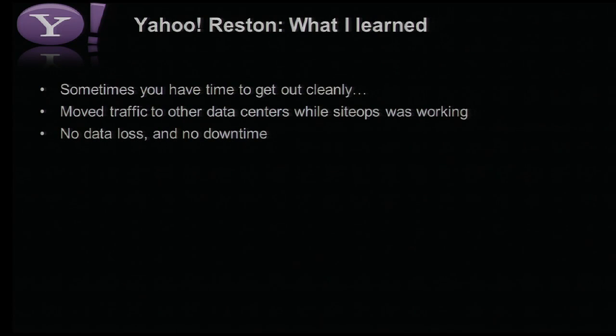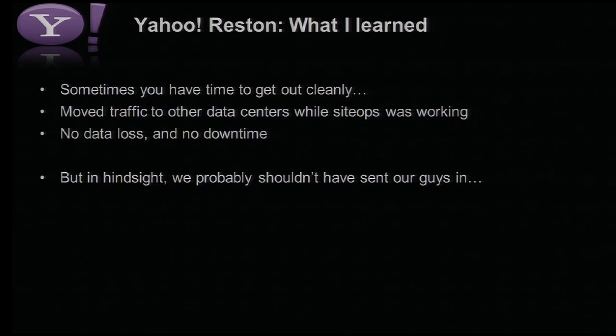Data center went up to 130 degrees within minutes. We were sending our site ops in 5-minute shifts to cleanly shut stuff down. Now, in that case, what I learned, sometimes you do have time to get out cleanly. We were able to move traffic to other data centers while they were working. No data loss, no downtime. But in hindsight, probably shouldn't have sent our guys in there.